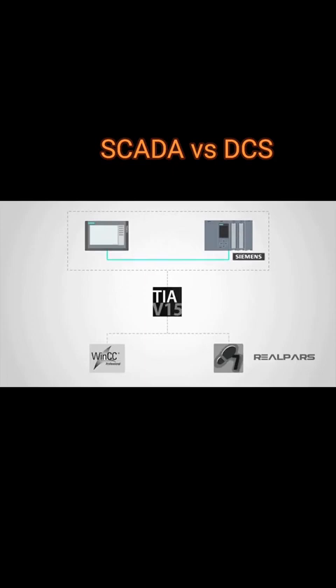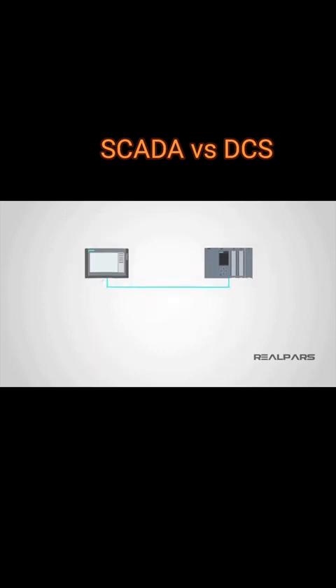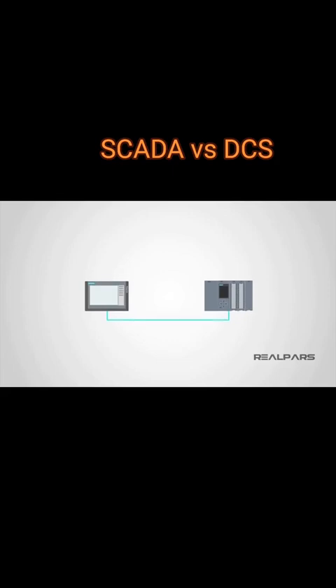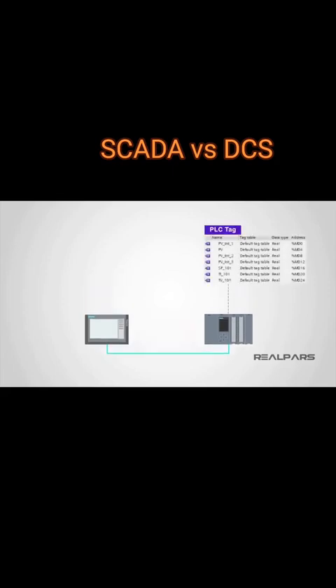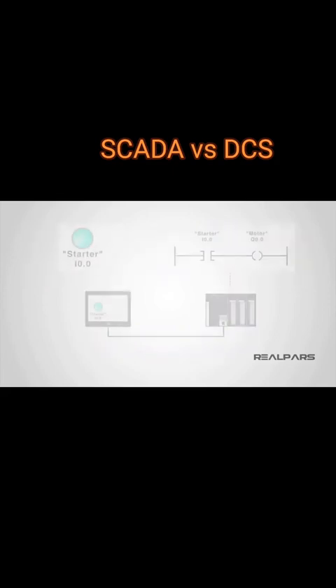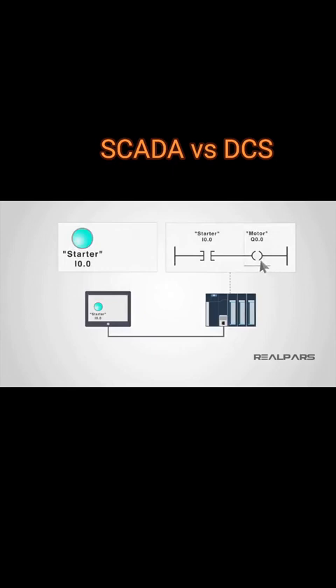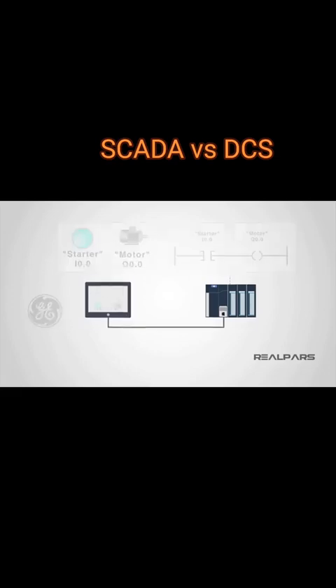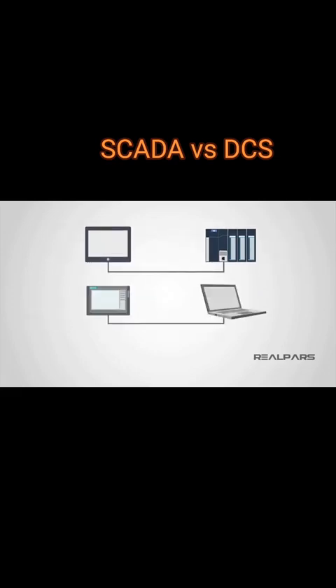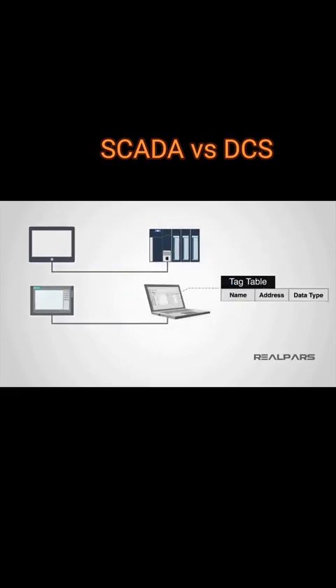Having the same vendor of PLC and HMI may seem to be an advantage, but as noted, the requirement for additional software is definitely not beneficial. You would also think that using the same manufacturer would allow you to have the tag database of your processor available for use in the HMI. Not necessarily true. Some vendors do have drag-and-drop capabilities, such as GE. However, most of them require exporting and importing, while others require the creation of the tags entirely from scratch.